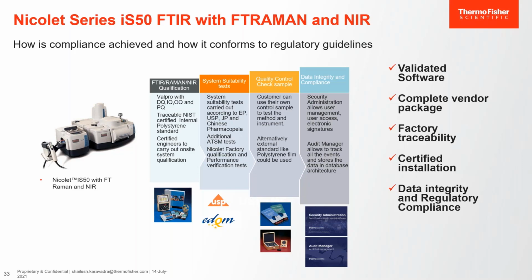We provide traceable standards again, depending on which spectrometer you use. All the tests are carried out with respect to all the pharmacopoeias, and additional ASTM tests for peak positions, for example for Raman spectroscopy, are carried out as well. Data integrity and compliance is done with Security Administration and Audit Manager, and both of these softwares are combined such that you get full compliance. And these are generalized softwares which can be used for most of our product portfolio.